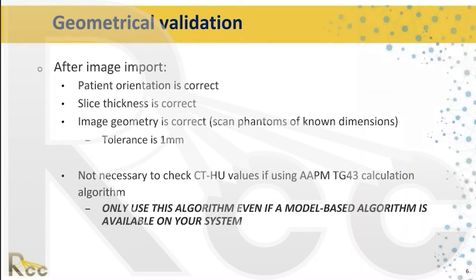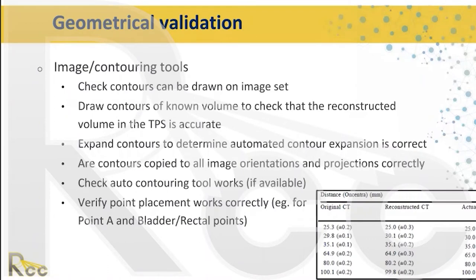It is not necessary to check CT Hounsfield units if you're using AAPM TG-43 calculation algorithms. Regardless of which planning system or dose calculation algorithm is used, we strongly recommend checking the performance against TG-43 or a similar formalism. We also validate contouring tools by contouring known volumes and checking expansions to ensure those dimensions are correct.